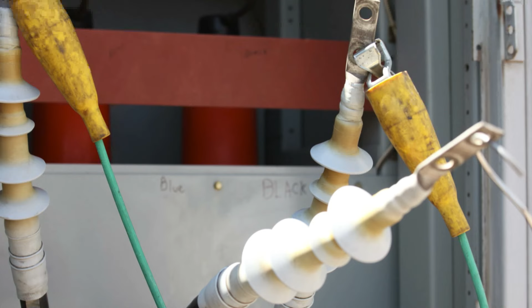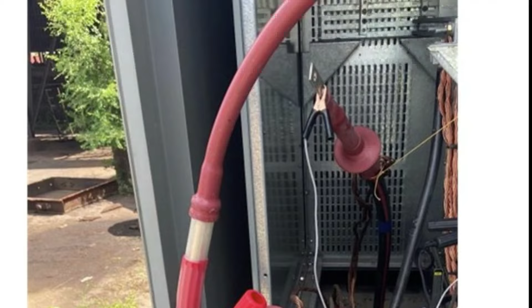Testing a 5 kV 20-foot run, single phase going to a parking lot lighting, you don't want to spend an hour offline 60 hertz partial discharge test on it. The amount of time and effort to do that test is probably more than the cable is worth. If you look at another example, the backbone medium voltage incoming feeder for a critical data center, that one you may spend a lot extra time on and verify that it is performing under very harsh conditions, because that'll tell you if it'll last another 3, 4, 5 years until your next maintenance cycle.